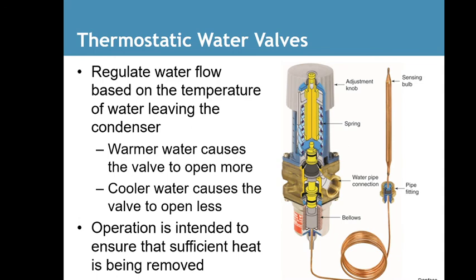Thermostatic water valves work just like a thermostatic valve on a mixing device, kind of like a TXV. Regulates the water flow based on the temperature of the water leaving the condenser. Warmer water causes the valve to open more. Cooler water causes the valve to open less. Operation is intended to ensure that sufficient heat is being removed.